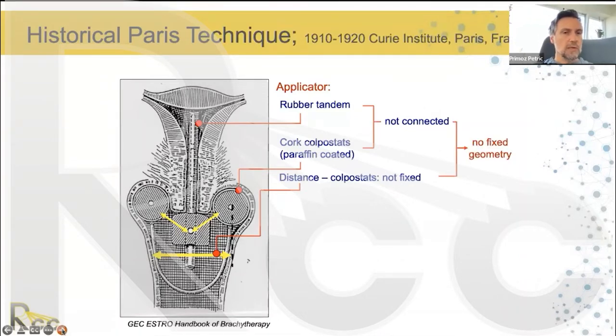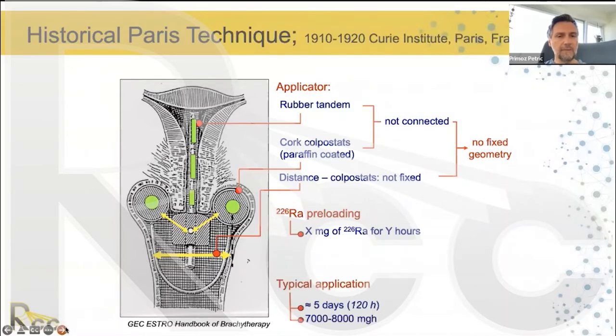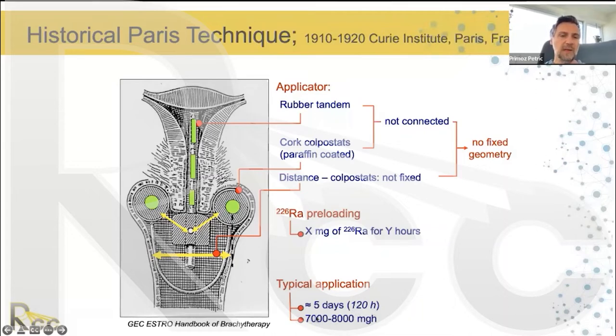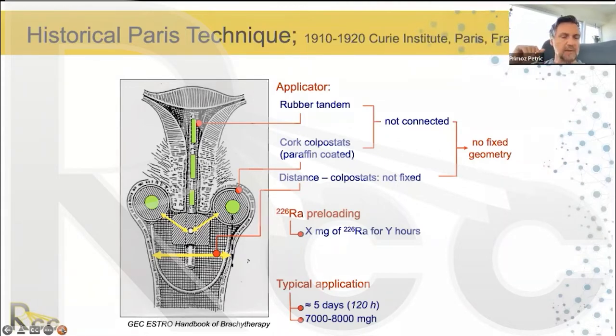These historical applicators had no fixed geometry, which is not a characteristic of modern applicators. The applicator was loaded with radium-226, and a certain amount of radium was left in place for a certain number of hours to arrive at the typical application described in terms of milligram hours of radium. Around 120 hours would produce typically 7,000 to 8,000 milligram hours of radium. These units of milligram hours still remain relevant nowadays, converted to SI units, but with a link to this historical tradition.